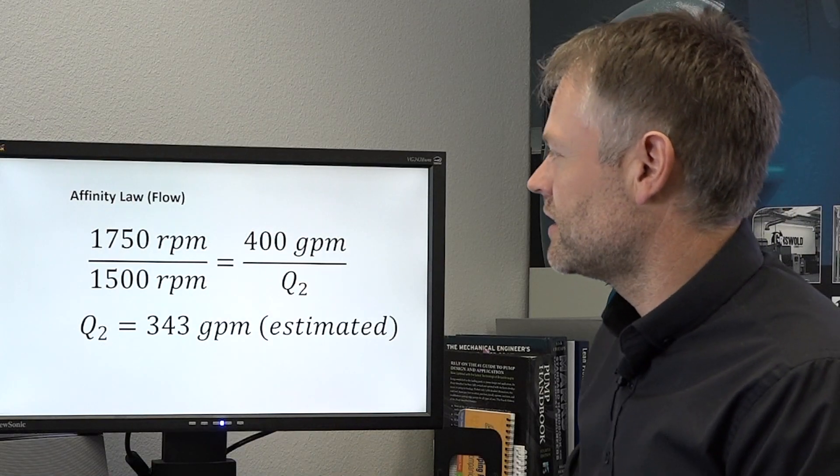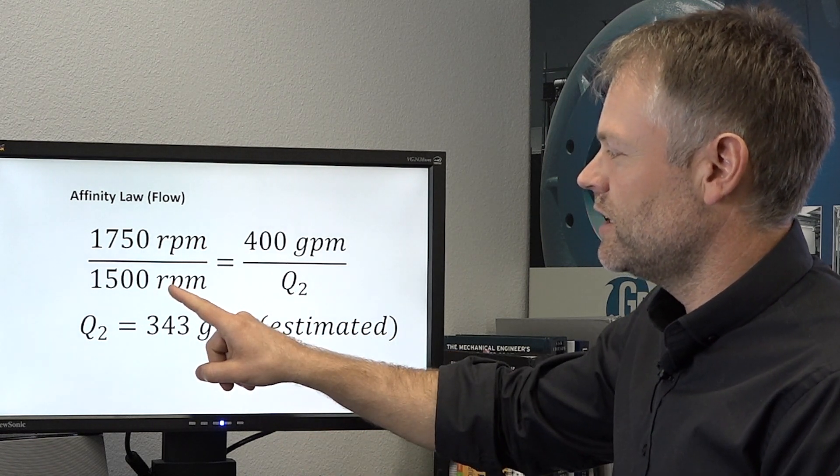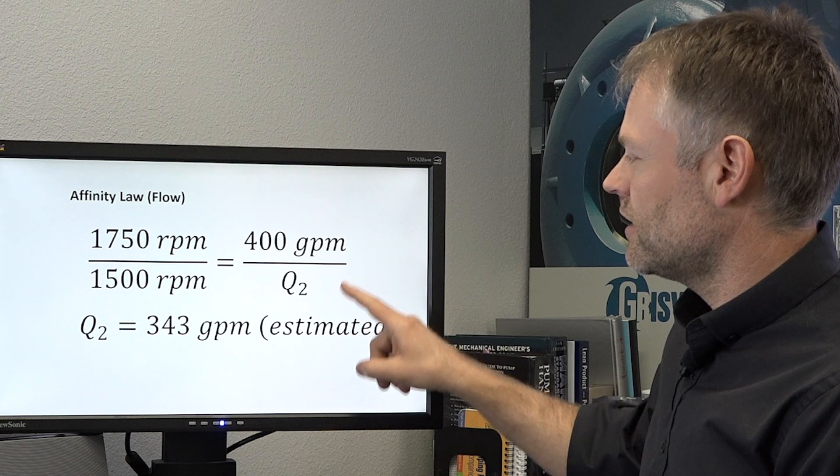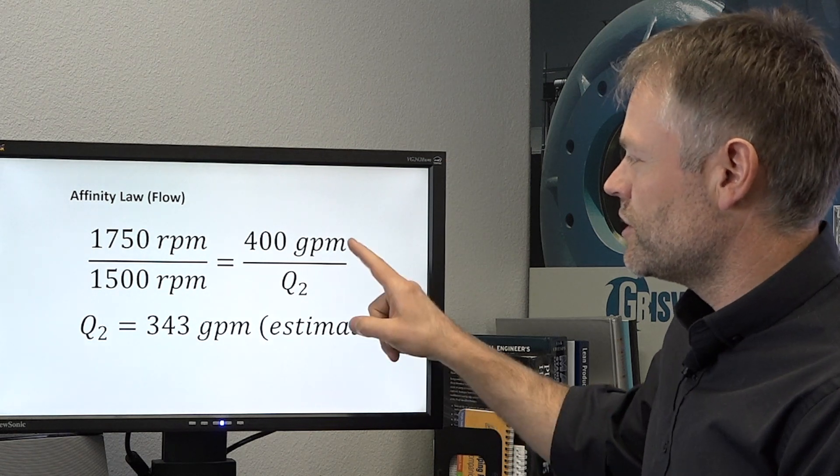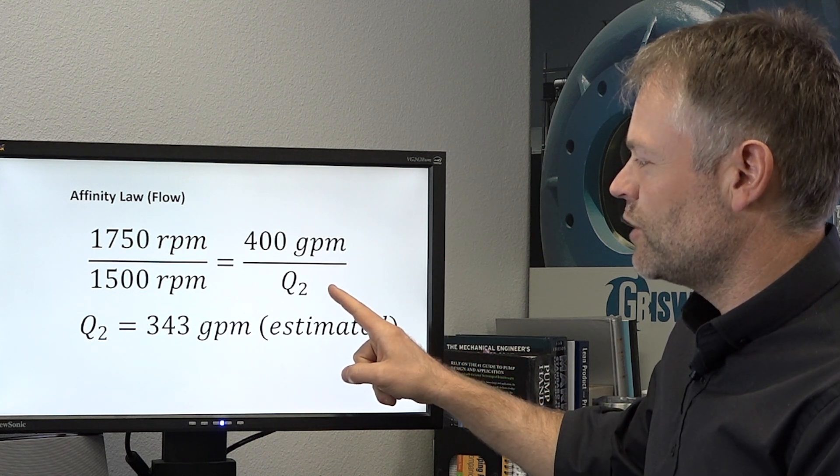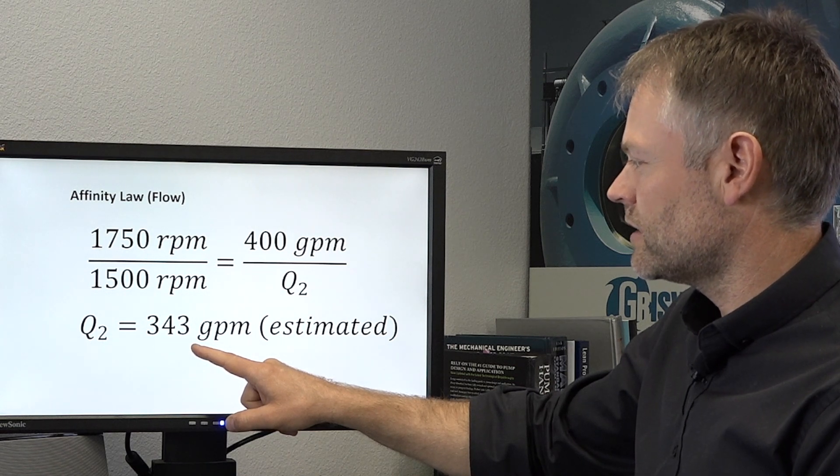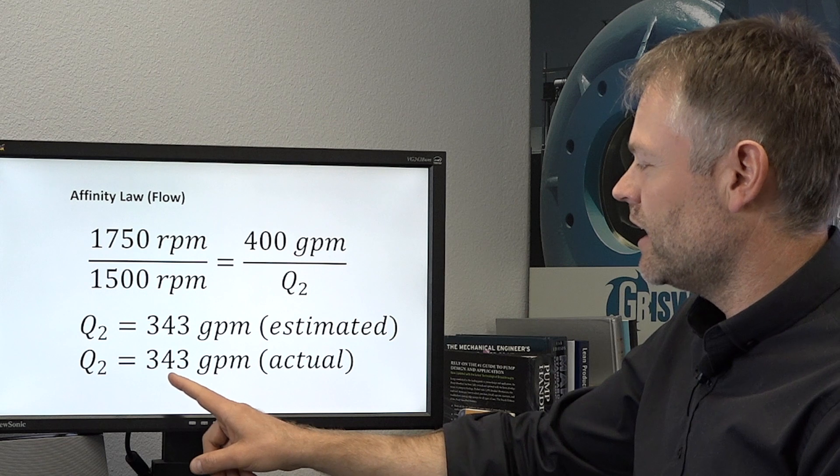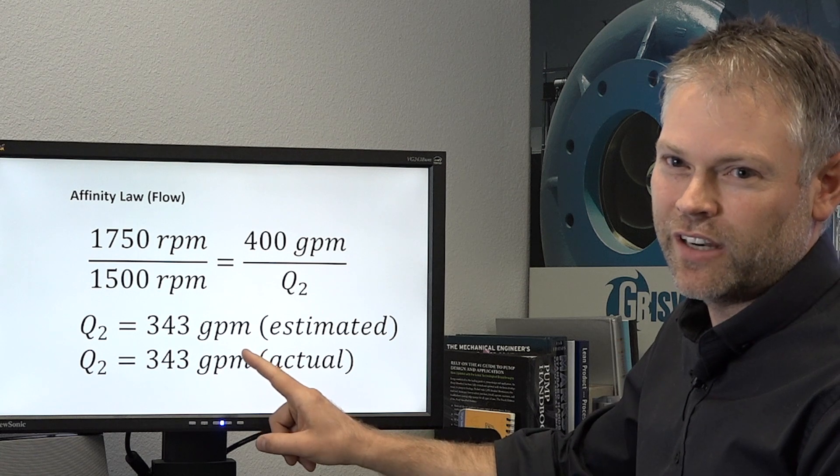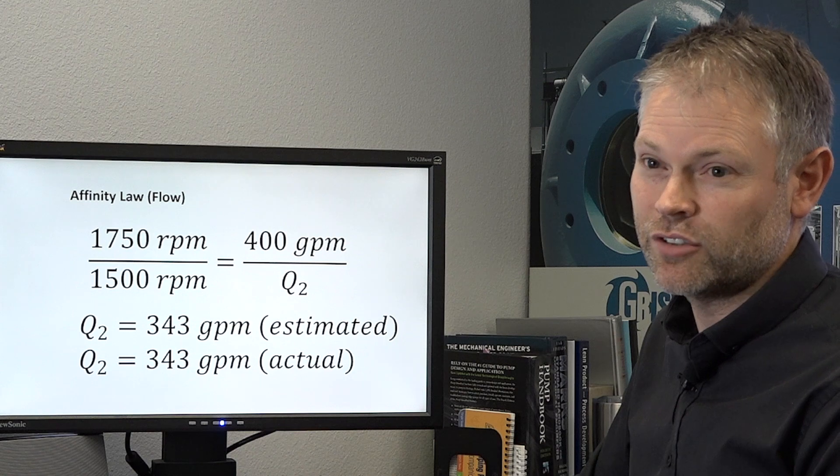As we saw in the test lab, we started with the pump operating at 1750 rpm and we reduced the speed to 1500 rpm. We can use these to help calculate the change in flow. We started with 400 gallons per minute, and by calculating for our estimated future flow, we would expect the pump to operate at 343 gallons per minute. When we were out at the test lab we saw that the actual flow was 343, so as you can see the pump affinity laws did a very good job of estimating the pump's performance after changing speed.